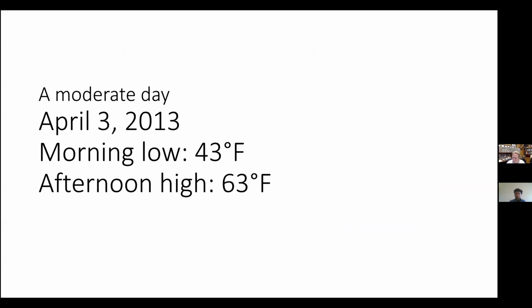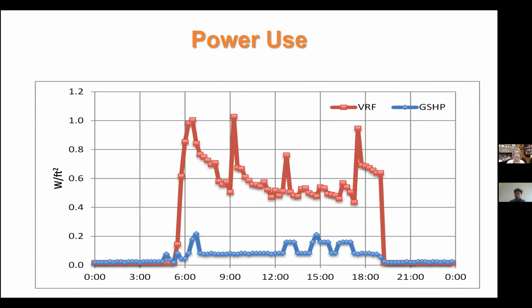So to try and explain some of this, here's an example from what I call a moderate day. It was April 2013, 43 degrees in the morning and 63 in the afternoon. We still have cooling loads in an office building. But if you plot the power usage for the day, there are setback thermostats at night, and in the morning, and again this is watts per square foot of floor area, you see this little blip up where probably one heat pump is coming on, another little blip up where another heat pump's coming on, and then in the morning maybe three heat pumps come on, and then maybe we drop down to 2, but it's pretty typical. We're not running all the heat pumps that we have. We're only running a few at any one time.